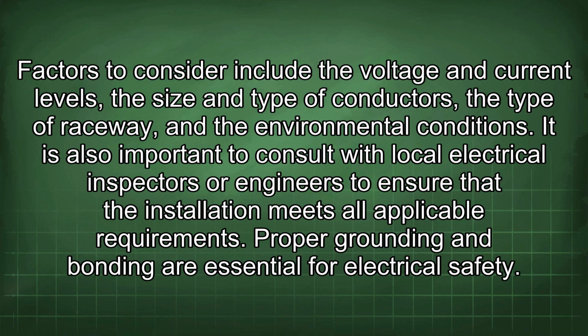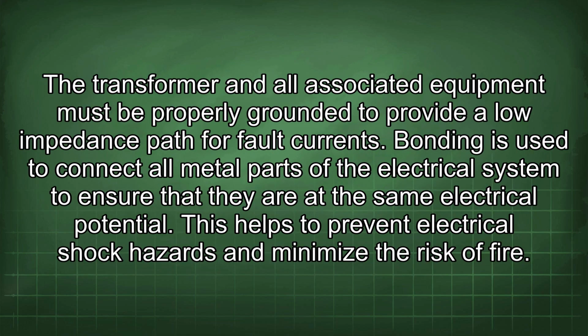Factors to consider include the voltage and current levels, the size and type of conductors, the type of raceway, and the environmental conditions. It is also important to consult with local electrical inspectors or engineers to ensure that the installation meets all applicable requirements. Proper grounding and bonding are essential for electrical safety. The transformer and all associated equipment must be properly grounded to provide a low impedance path for fault currents. Bonding is used to connect all metal parts of the electrical system to ensure that they are at the same electrical potential. This helps to prevent electrical shock hazards and minimize the risk of fire.